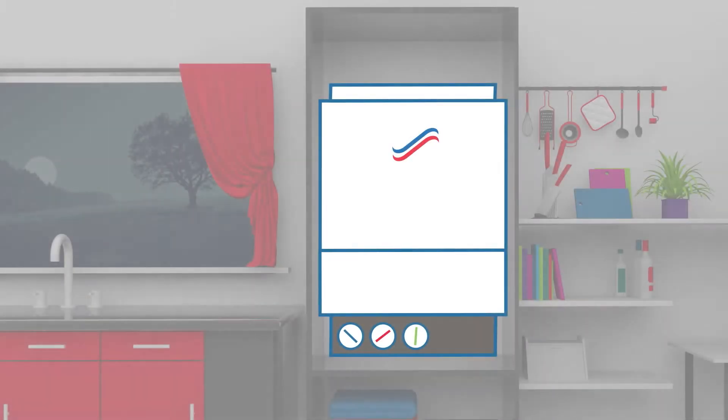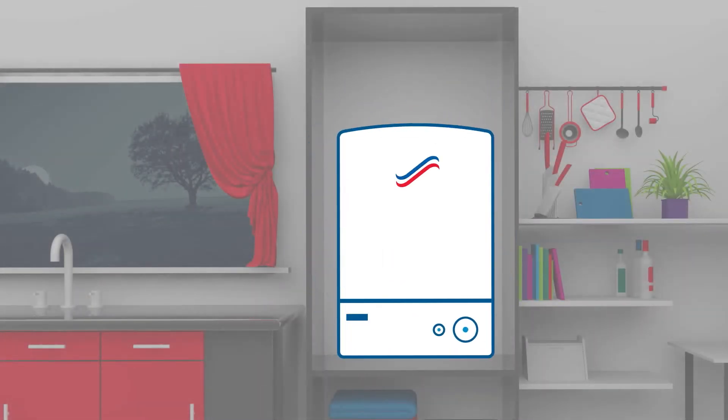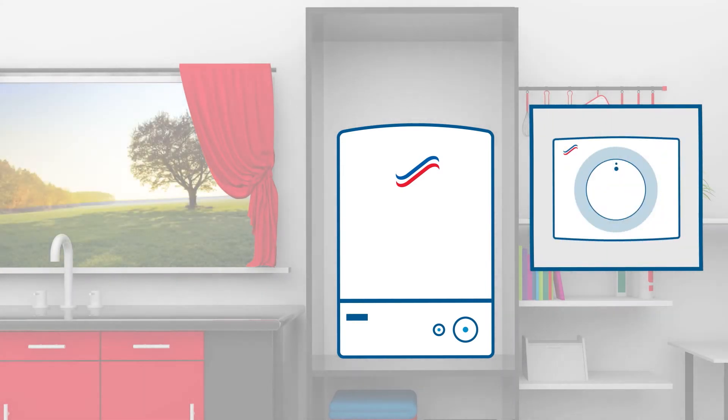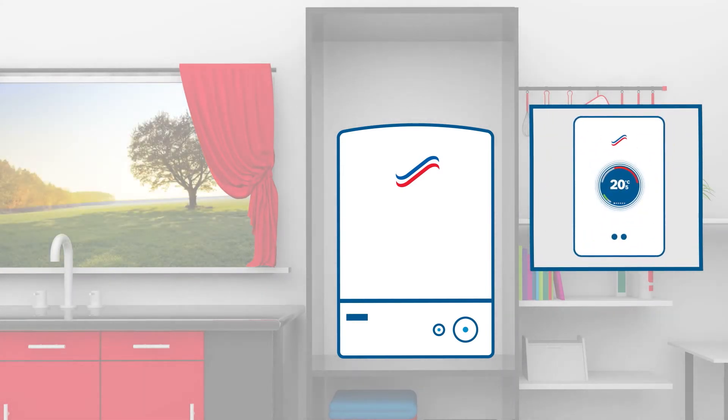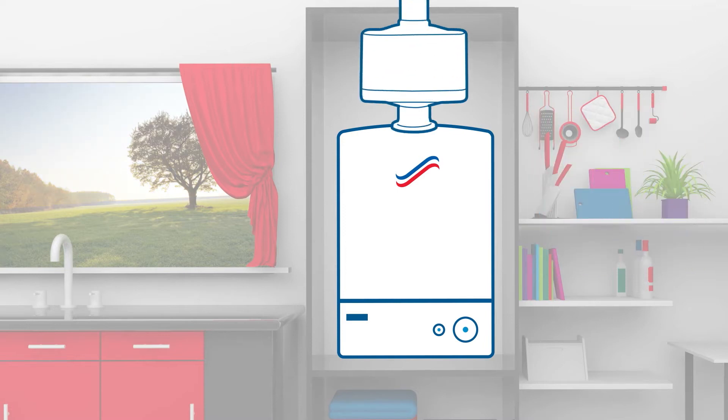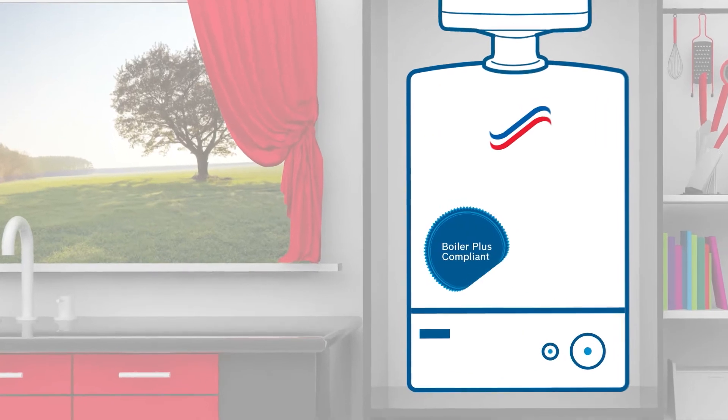From April, any gas-fired combi boiler replacement installations in England must be installed with a time and temperature control along with either a smart, load or weather compensation control or a flue gas heat recovery unit.